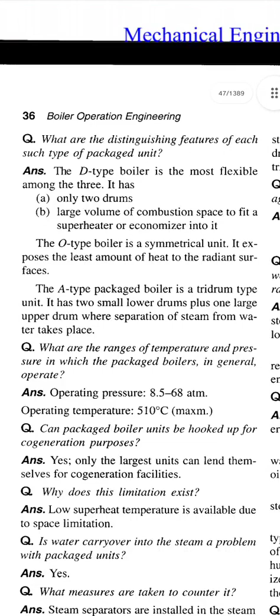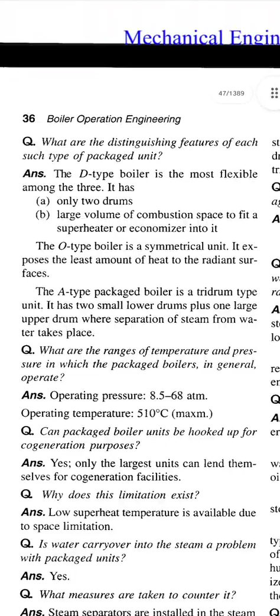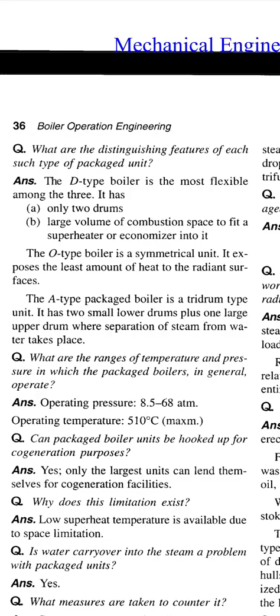The next question: what are the distinguishing features of each such type of packaged unit? The D type boiler is the most flexible among the three. It has only two drums, and a larger volume of combustion space to fit a superheater or economizer into it. The O-type boiler is a symmetrical unit. It exposes the least amount of heat to the radiant surfaces. The A-type packaged boiler is a tri-drum type unit. It has two smaller lower drums plus one large upper drum where separation of steam from water takes place.